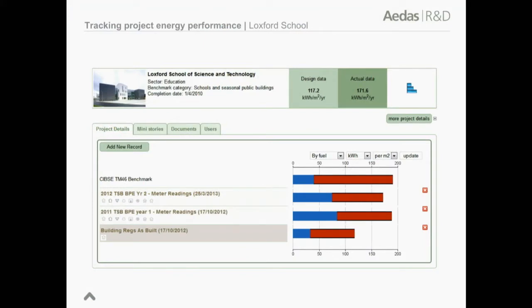Looking at this in a bit more detail in one of the education buildings, again you see this was the building regs data, that's the first set of meter readings, second set of meter readings. We can't tell much from that. But as soon as you go into the detail data, you can see that the heating is a hell of a lot more - the ground source heat pumps didn't work. The lighting's about 3 times more, the fan power is more, cooling loads are more. So we could start looking at the building.